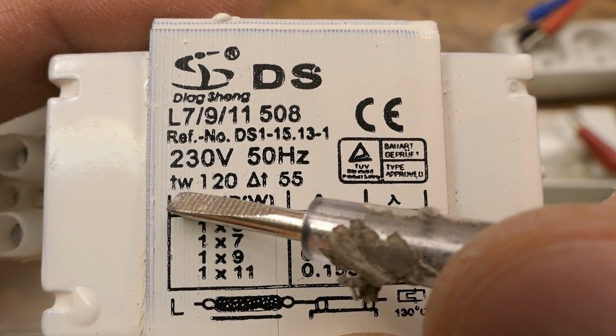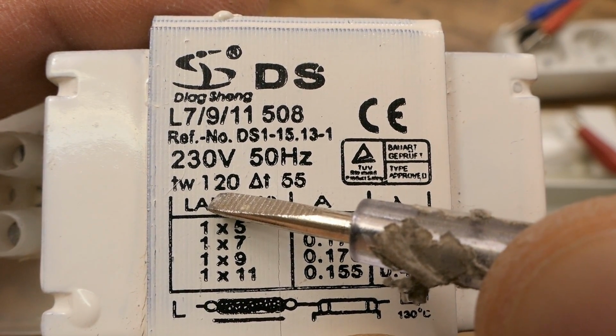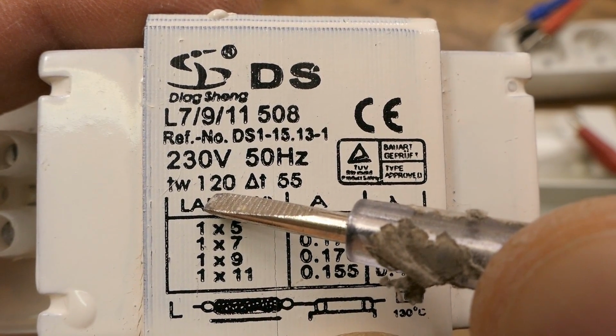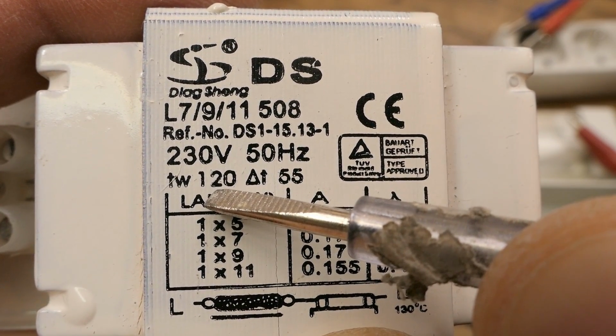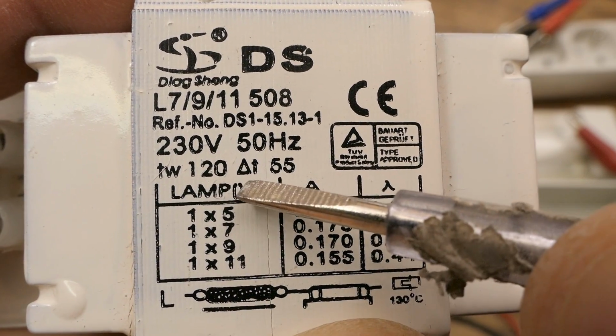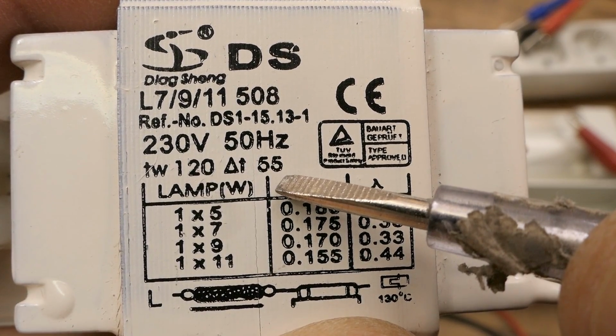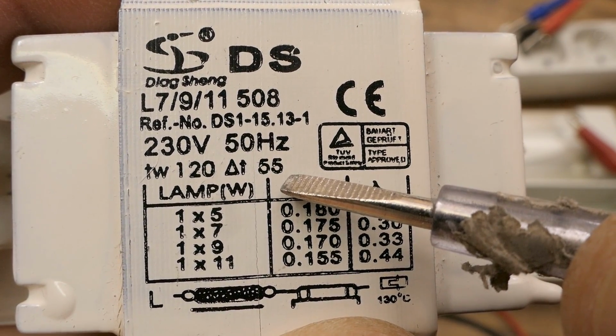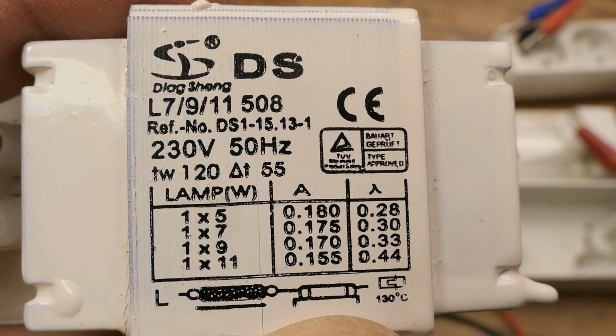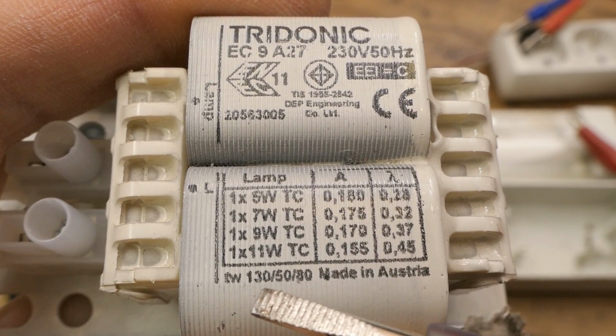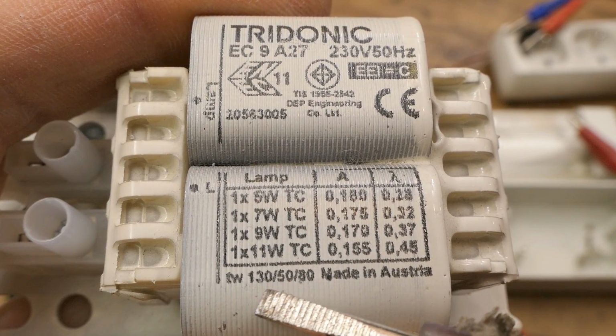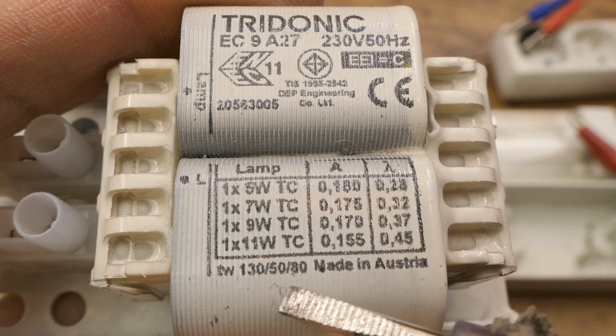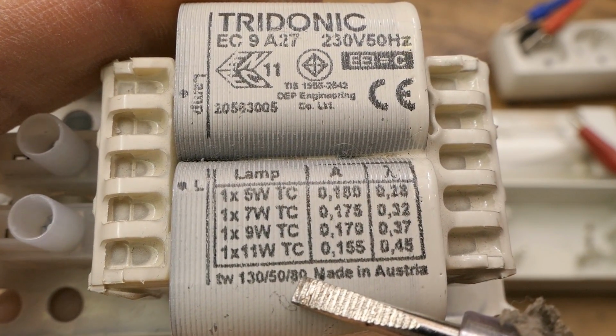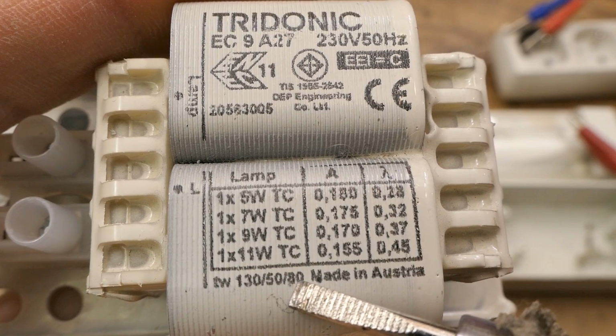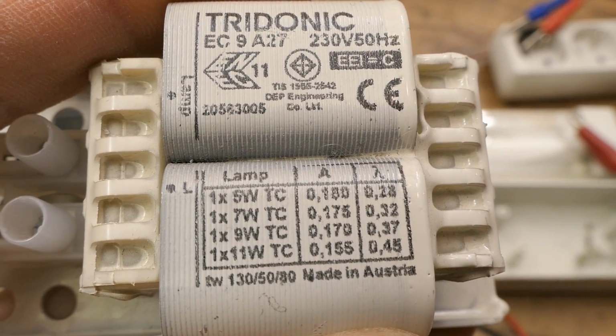Now I guess this is the temperature of the winding, maximum 120 degrees Celsius. This is the temperature at which the winding has 100,000 hours life, and the delta T is 55 degrees Celsius - that's basically running 55 degrees Celsius above ambient. And this one has 130 degrees Celsius winding temperature, 50 degrees above ambient, and I guess this is the abnormal temperature rise, for example when the starter is stuck and the inductor basically sees more voltage.